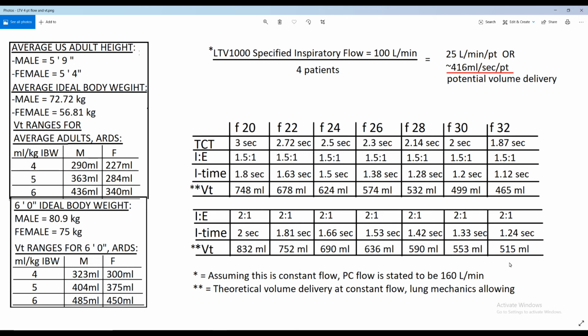Whether or not the patient would get that, I know that's going to depend on a lot of things, but it's actually looking pretty hopeful because even if we had bigger patients, so let's say they were 6 feet or maybe even a little bit bigger, your big, 6 foot or more males, and they're getting 6 mLs per kilo, they're going to need 485, if they were taller, maybe somewhere around a little over 500. Well, we're still comfortably able to theoretically flow over 500 mLs to each patient, even if we have high respiratory rates and we have long inspiratory times.